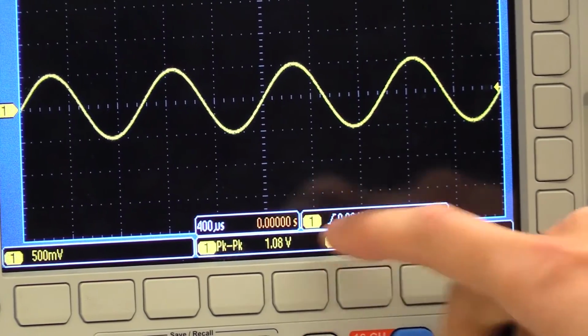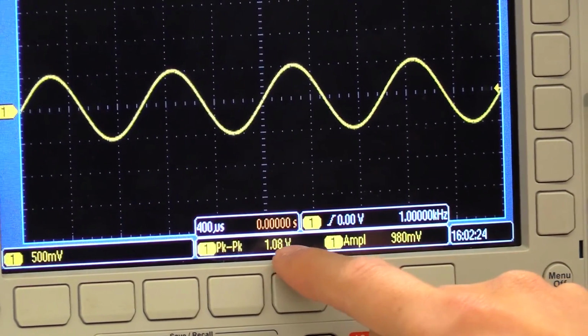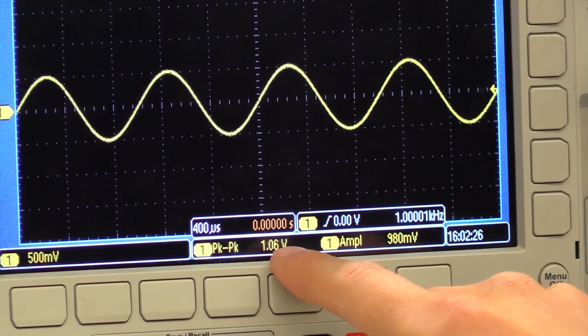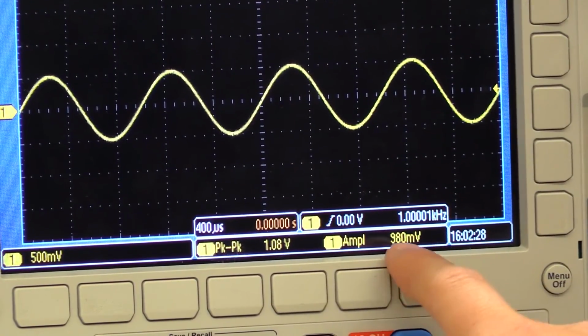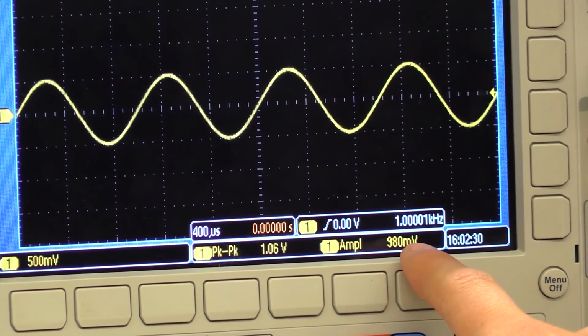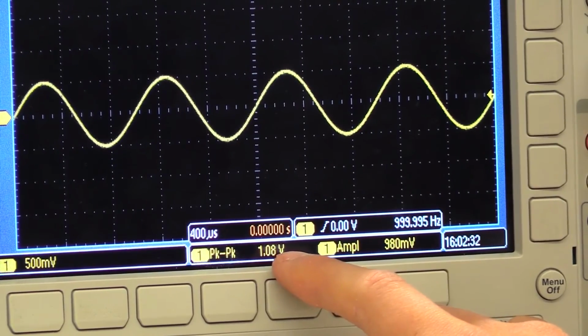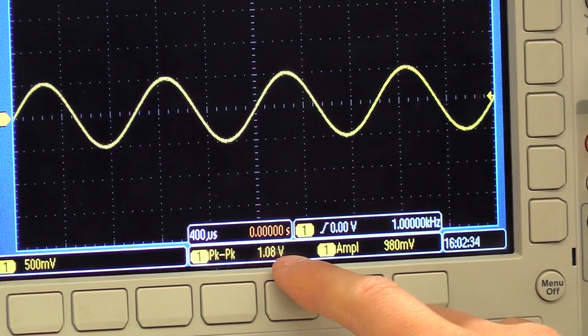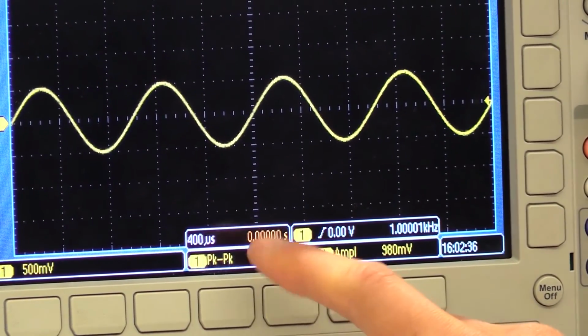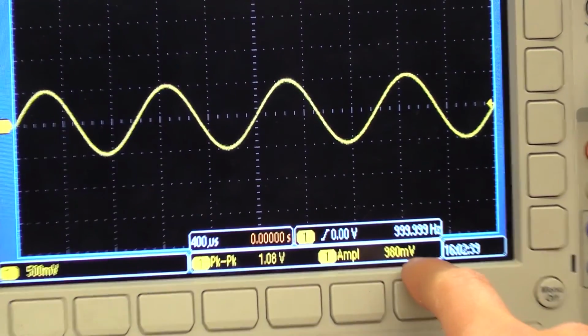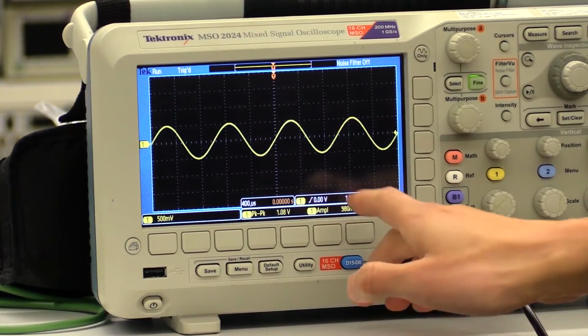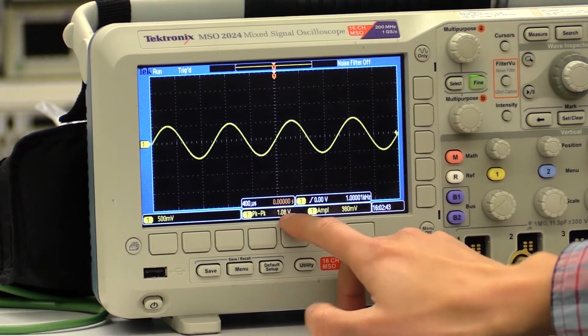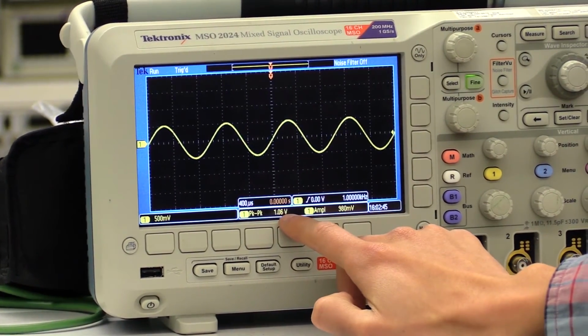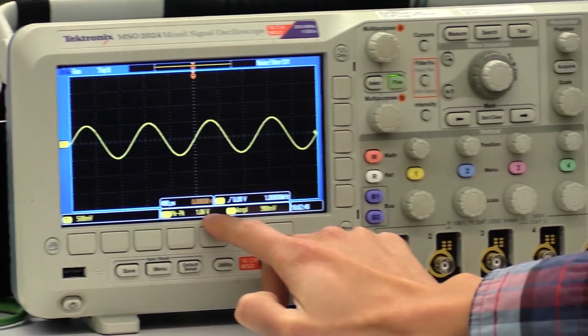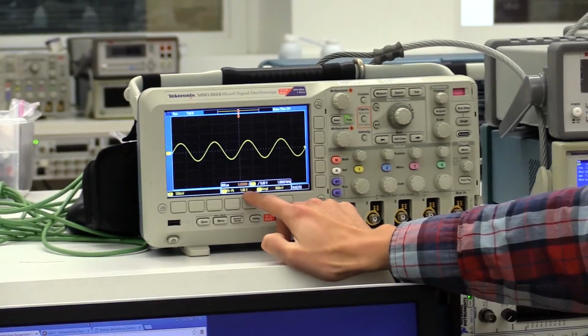Measurement 1 is peak to peak, which is giving us about 1 volt, and amplitude is also about 1 volt. If we notice here, the peak to peak measurement seems to be varying a lot more than the amplitude measurement, because, like I said before, the peak to peak will give you the active reading of all the spikes and noise that the signal carries, whereas amplitude is kind of negating all of those. So amplitude is very steady, whereas peak to peak, even with the arbitrary waveform generator, is still showing some variations.